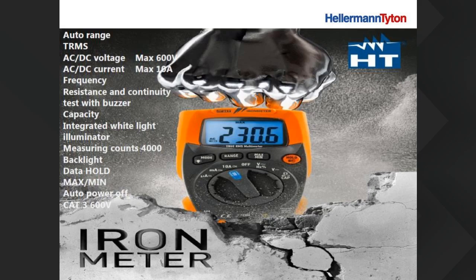This meter is an auto-ranging AC/DC meter to the maximum of 600 volts. Maximum that is only with test leads. It's a frequency meter, resistance and continuity with a buzzer. It measures capacity. It's got an integrated light, white light illuminator by default, meaning it's got a flash as well. And yeah, this is a very, very strong and durable meter.